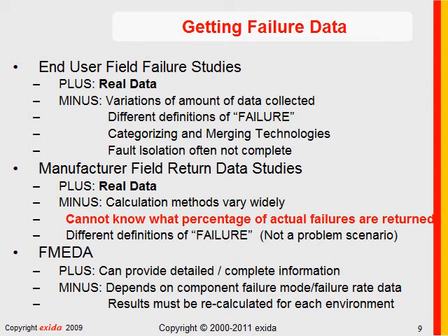I was taught to assume that every failure that was returned to us was a failure, and all failures were returned to the manufacturer. And so I would simply take the number of real failures that came in the door, divide by my estimated number of operational hours, and I can tell you in hindsight I was coming up with wildly good failure rate numbers, because those assumptions I was taught are simply not valid.